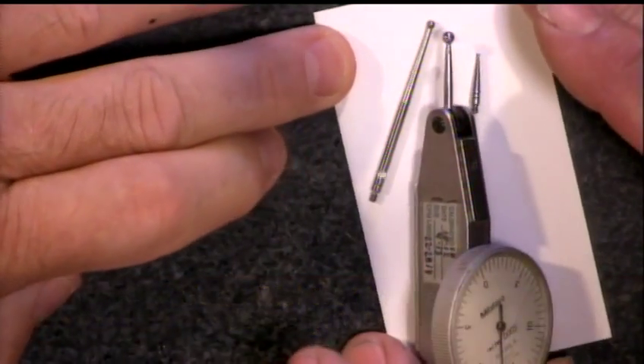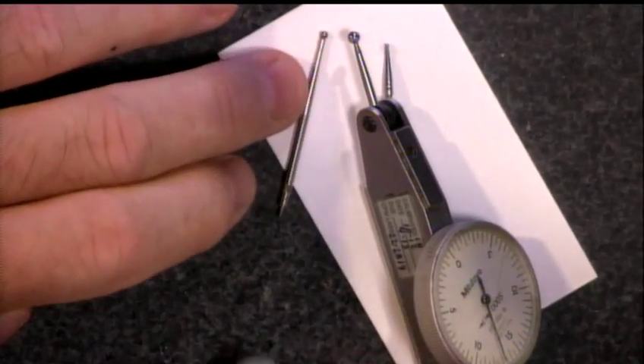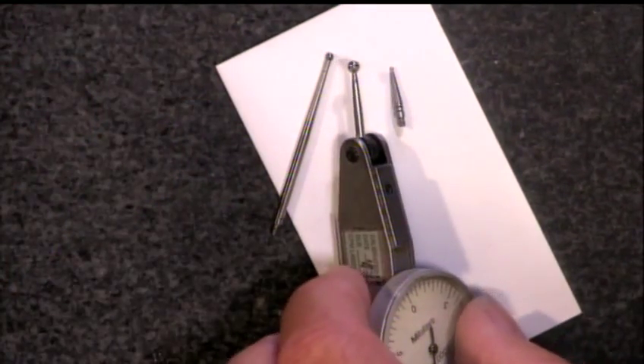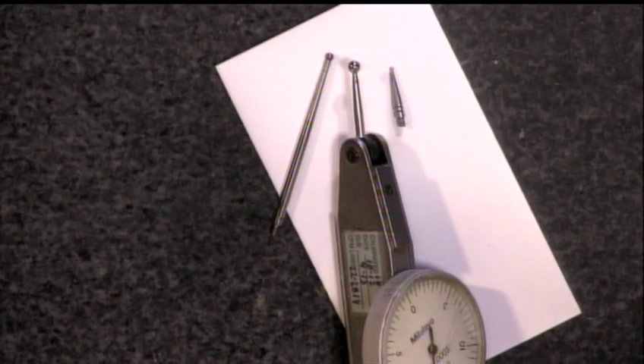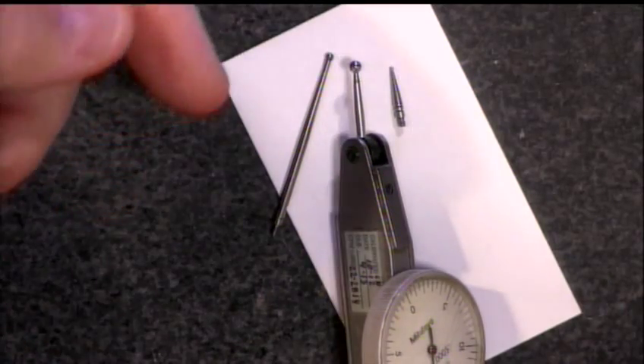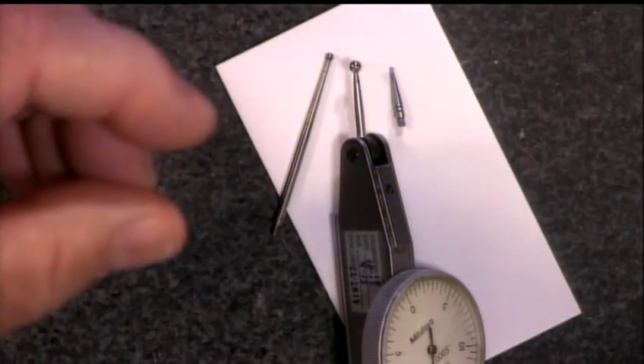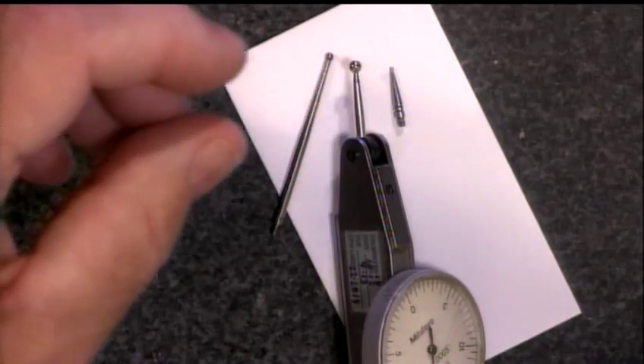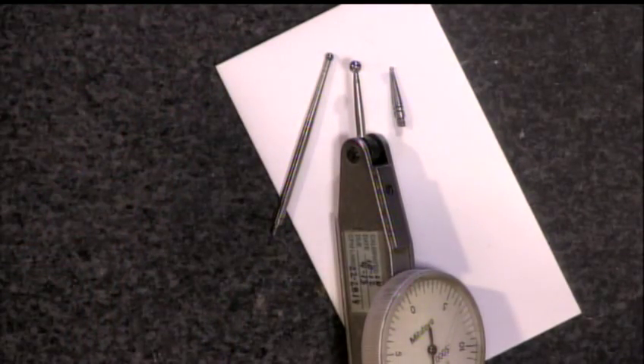I have 3 different length contact points. The question always comes up, and a lot of people will ask me this: I want to use a different ball diameter, the ball's too fat, it won't fit in the right area for me. Is that going to change anything? The answer is the ball diameter is irrelevant. The ball diameter is up to the user. The length is what determines the accuracy of the indicator, and each indicator is made for one length only. You can't interchange lengths and get a correct measurement. So you're saying you could have a big old ball, but as long as it's the right length, you're good. The ball diameter doesn't matter.